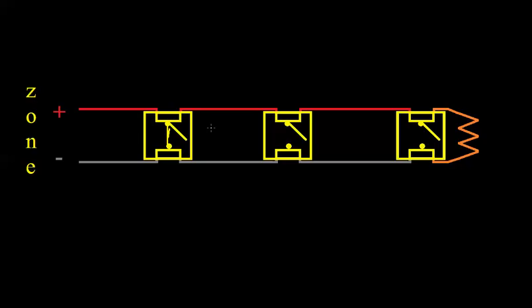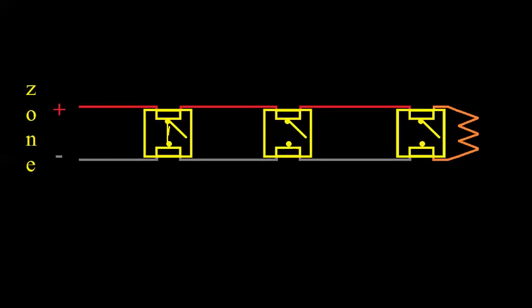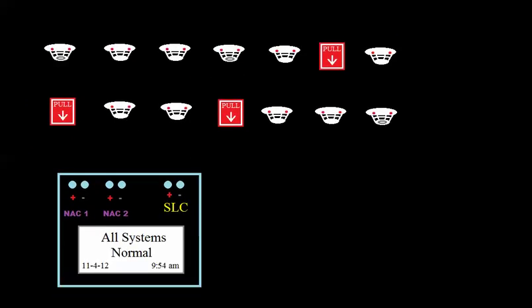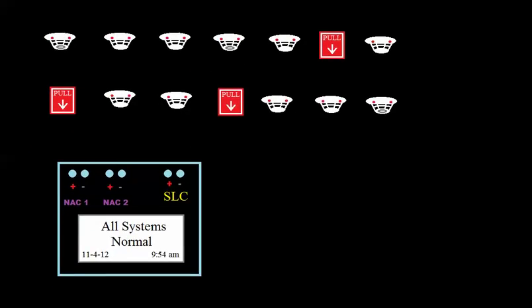That's not at all how addressable panels work, or intelligent panels. You'll hear there is some difference between the terminology, between addressable and intelligent. But from my experience, the two terms are used pretty much interchangeably. So we're not going to spend a lot of time on that. An addressable panel or intelligent panel uses something completely different. It uses data communication to communicate with all of its initiating devices.